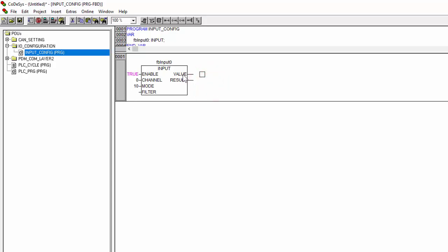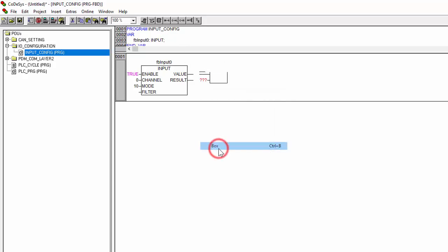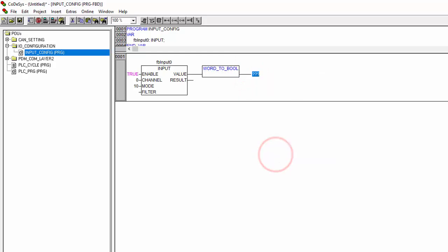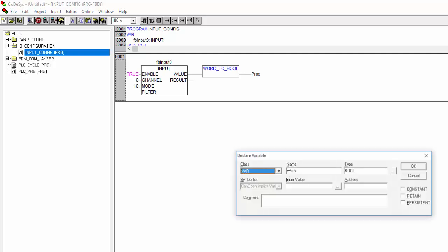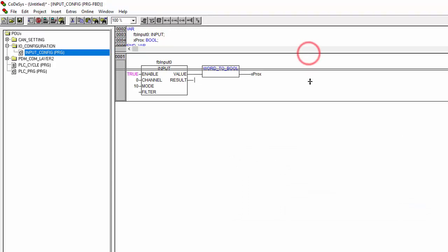Then enable is true. The channel should correspond to the channel where you have connected your sensor. In my case, the digital input is connected to channel zero. So I make it zero and my mode. Once again, if I need to know the mode, I just right click on input function block and click zoom. It takes me directly to the library, select input and you can see the mode now is number 10. So I make the mode number 10 and I delete this part. Now, this value which is the output variable is a word. You can use it as a word, but since it's a boolean value, I just add another box. So right click and say box and then make it word_to_boolean. And then right click, assign and just say xprox and declare the variable as a local variable to start with. So that's the setup for our first input, which is the digital input.